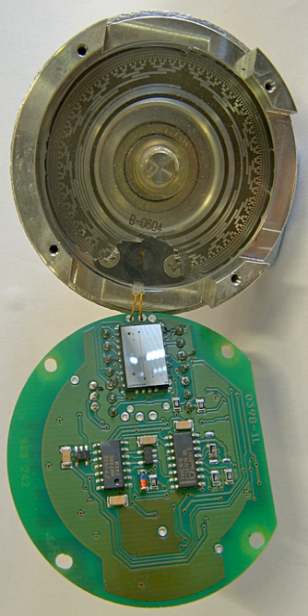Topic: Optical absolute encoders. The optical encoder's disc is made of glass or plastic with transparent and opaque areas. A light source and photo detector array reads the optical pattern that results from the disc's position at any one time. The gray code is often used. This code can be read by a controlling device, such as a microprocessor or microcontroller, to determine the angle of the shaft. The absolute analog type produces a unique dual analog code that can be translated into an absolute angle of the shaft.